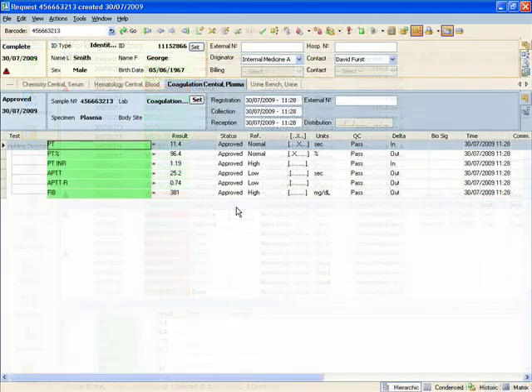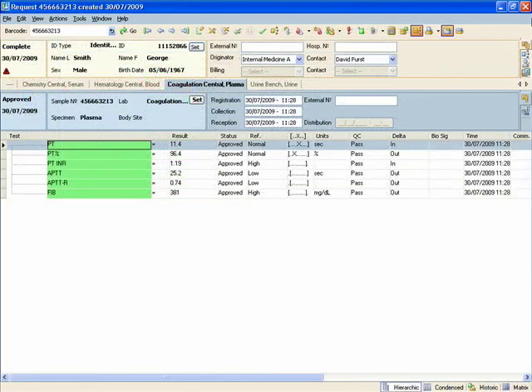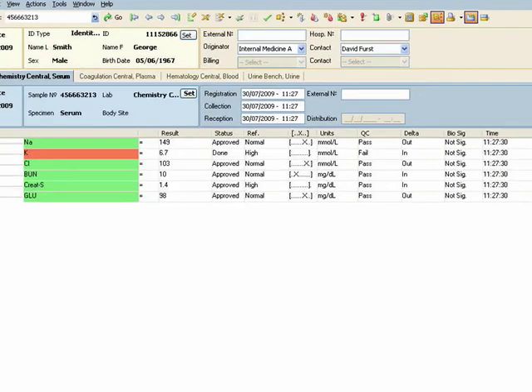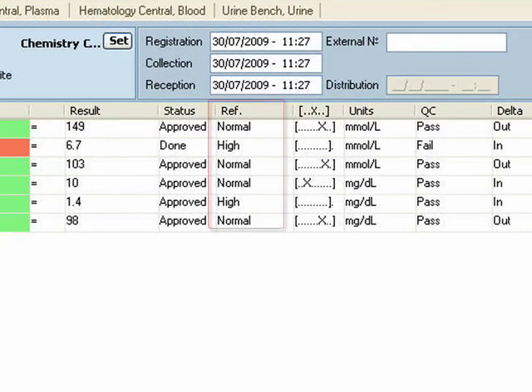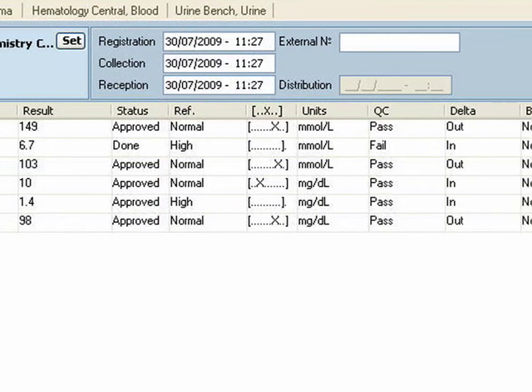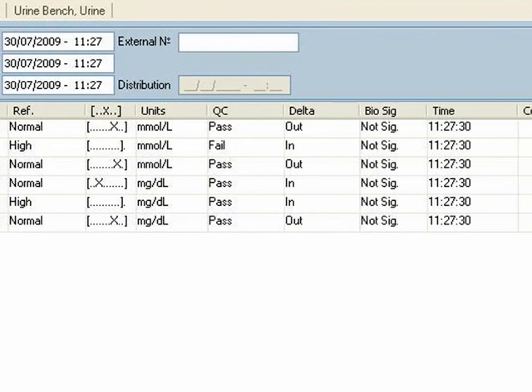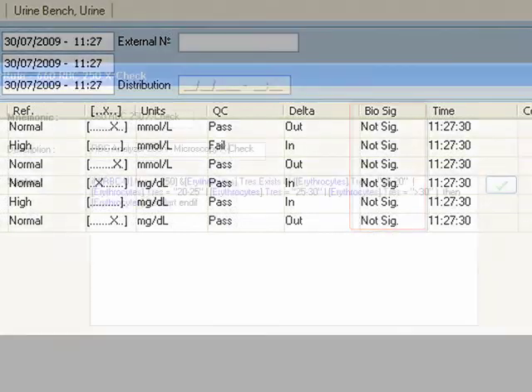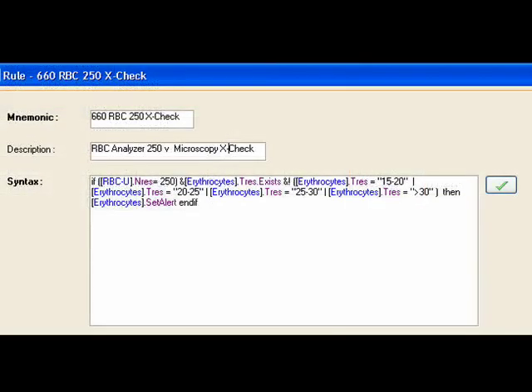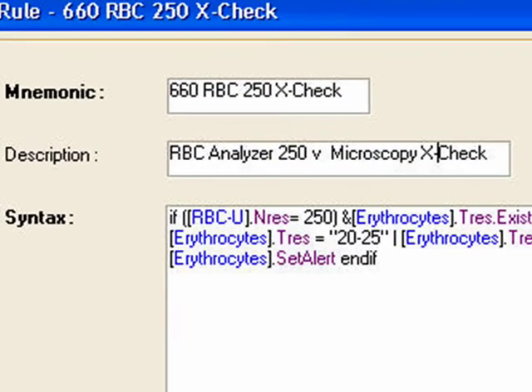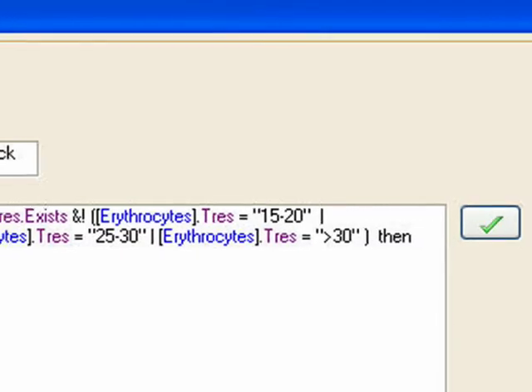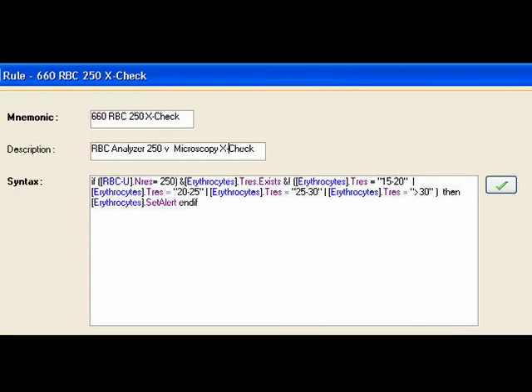Reference ranges can be constructed for any user-configurable patient type. Each current result is further checked against historical values for change of range, absolute or percentage differences, and the presence of biologically significant difference. eLab's expert system can apply individually designed, sophisticated, and complex rules to assist result validation.